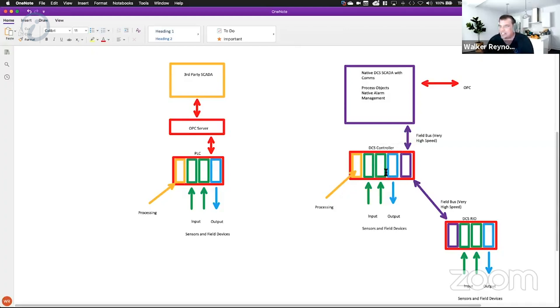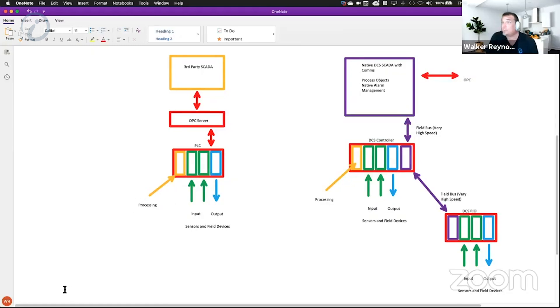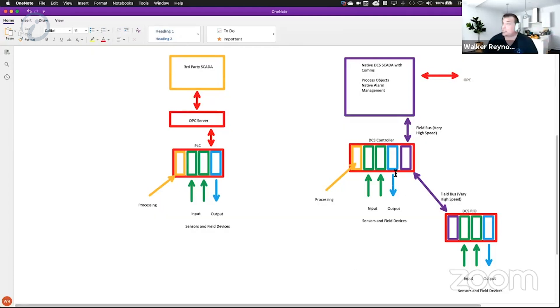I've got my DCS controller, but I also have DCS remote IO. A PLC can talk to a remote IO rack, but it's generally going to do that over Ethernet/IP — talking to the other rack through Ethernet. This DCS controller, in basically every DCS system, is speaking to the DCS remote IO over fieldbus, which is blistering fast.